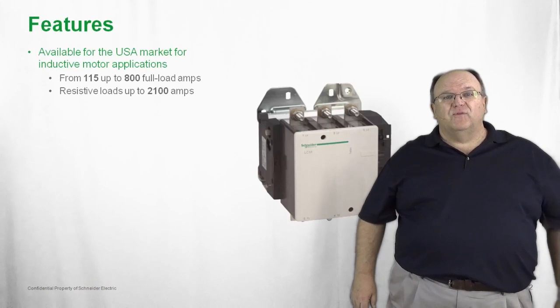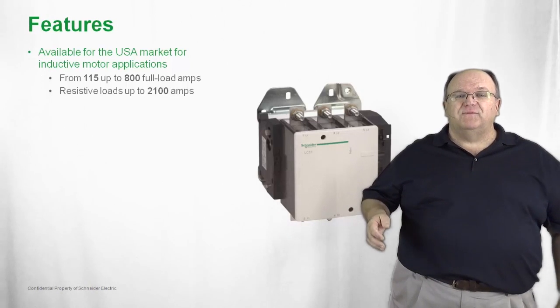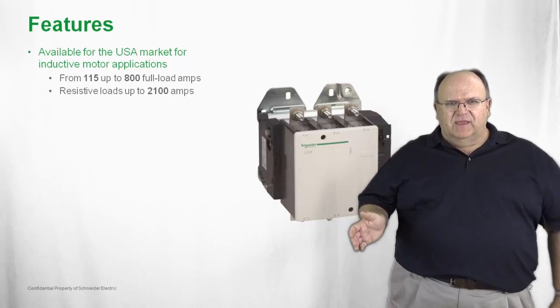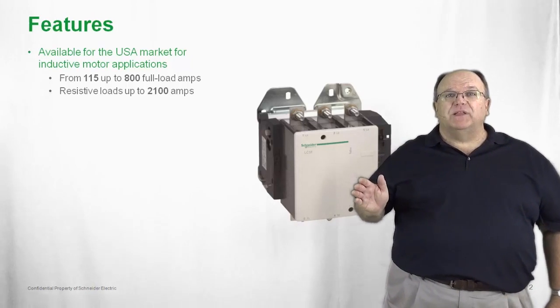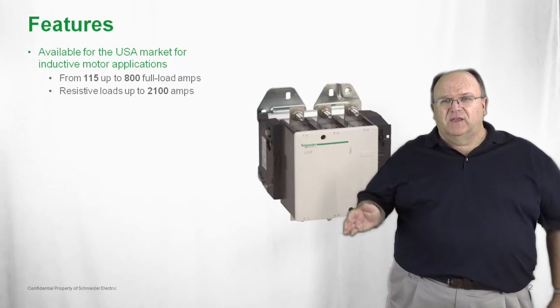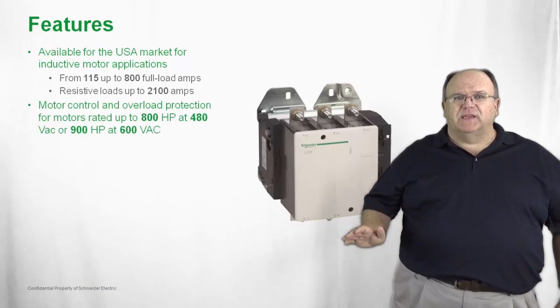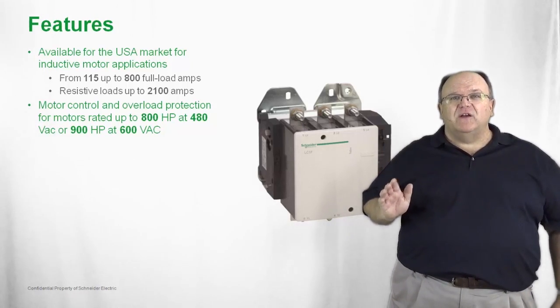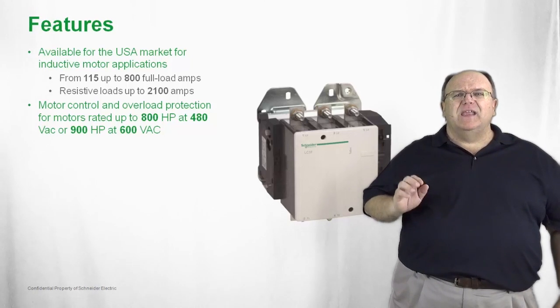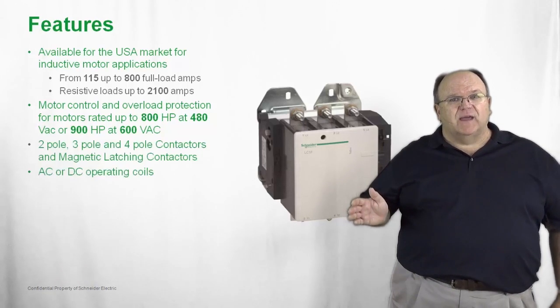Let's take a closer look at the features on the TeSys F. For the U.S. market, it's available in inductive rated or full-load amp ranges from 115 amps up to 800 amps. There are also specialty resistive-only rated versions available for applications up to 2100 amps. This is a really heavy-duty contactor line built for a wide variety of motor and non-motor applications. We even have specialty motor horsepower ratings up to 800 horsepower at 480 volts and 900 horsepower at 600 volts — really very large motors and unique applications.